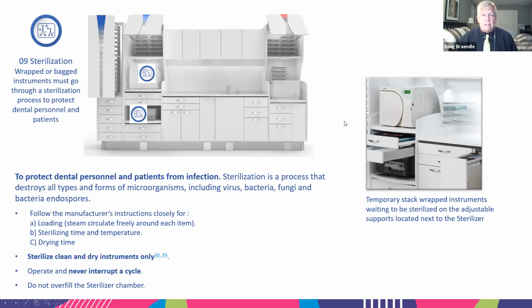We don't sell cassettes. So when we're pushing cassettes, it's because it is the easiest and the quickest and the most effective way of running the sterilization. We don't make a penny for people buying cassettes. But what I can tell you is that through the studies that our friends at Hu-Friedy have done, you can basically cut off 5 minutes per patient just by using cassettes. So once we kind of have the generalization that cassettes are a good thing to do, the nice thing about anybody's sterilizer, you can't really overload a sterilizer with cassettes as long as you keep the cassettes in the racks.